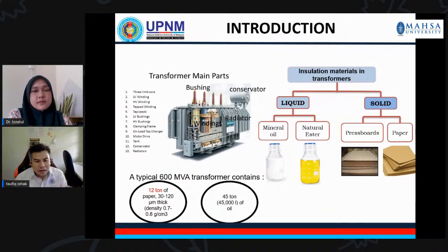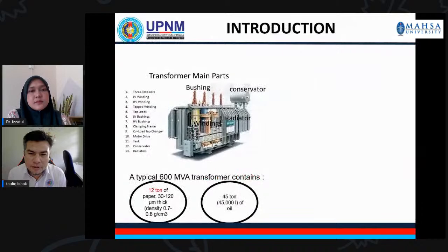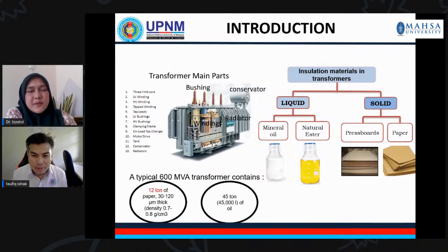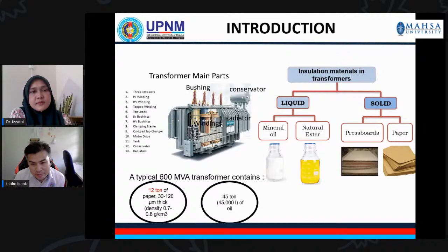So how can you imagine that? How much oil, or liquid, we use inside the transformer, as well as the paper or solid insulation. Quite a lot, right? The insulation of the transformer, like I said, has liquid parts and solid parts. For the liquid part, the common type of insulation liquid used is mineral oil. We also have silicone oil, synthetic ester and natural ester. Each of these fluids has its own unique physical and insulating properties, which determine their use.